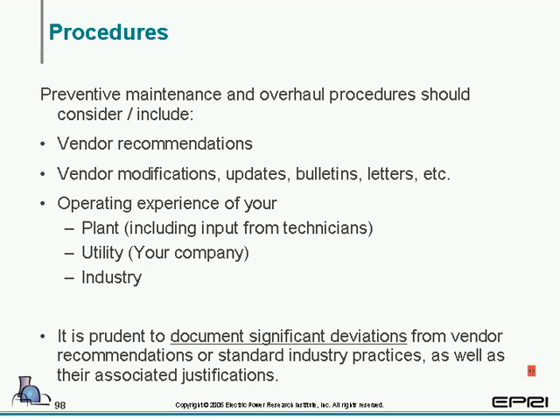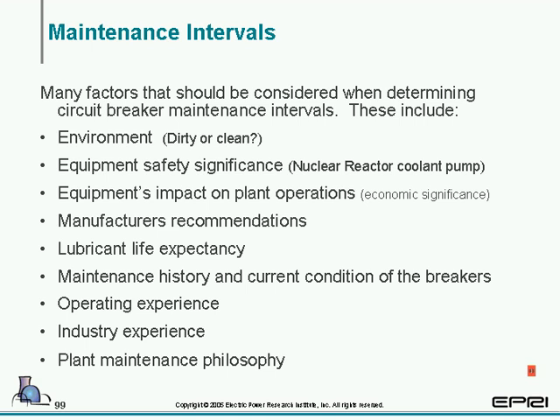If you have significant deviations from your vendor recommendations, for example, if your original vendor maintenance manual that came with your circuit breaker gives an overhaul interval of, say, 8 years, and you're significantly deviating from that, it might be wise to document that. There are many reasons for that. If you change jobs and the next guy comes in and wonders why you're doing something different than 8 years, he'll just move it back to whatever the manufacturer says, and that lesson learned will be lost. So, bottom line, document significant deviations from your vendor recommendations so that you'll have a record of it.